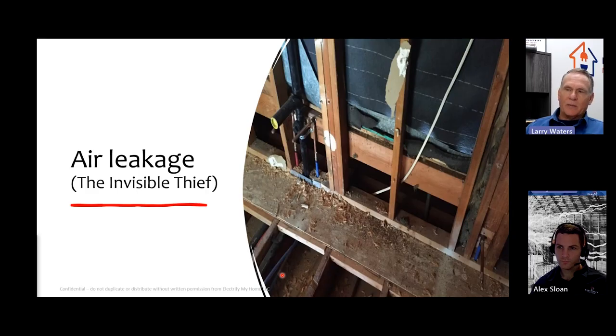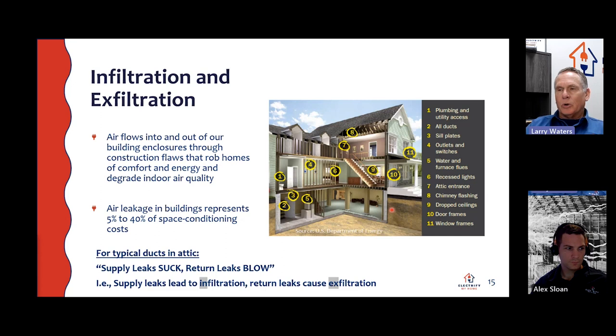So virtually what was happening here, because of this attic connection, this wasn't a 2-story structure that had a pressure boundary. It was really 2 1-story structures floating on a broken pressure boundary, and hot air getting in between the floors. And they wonder why their bills were huge and their upstairs would never cool down. So infiltration and exfiltration.